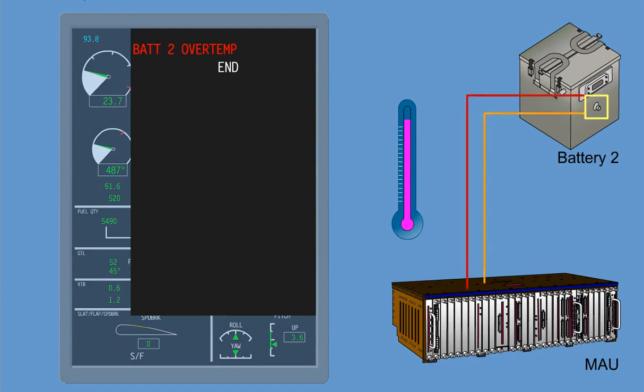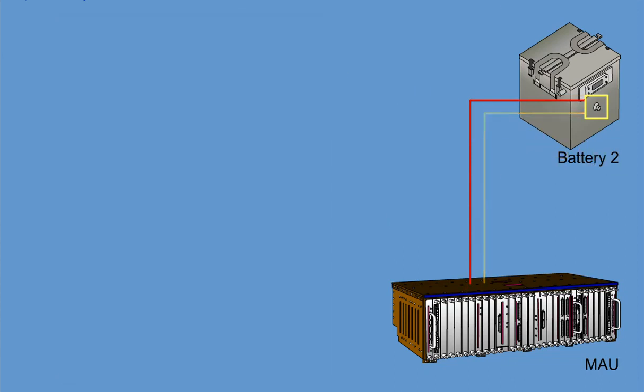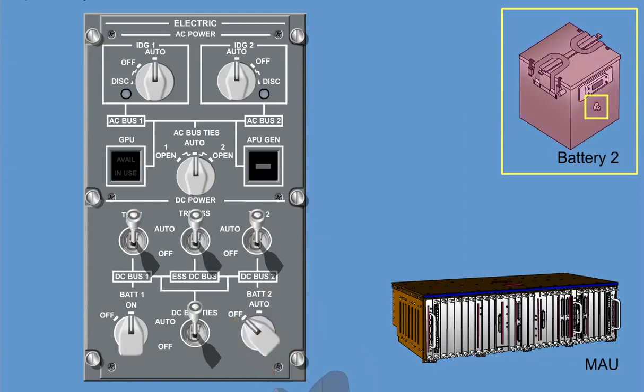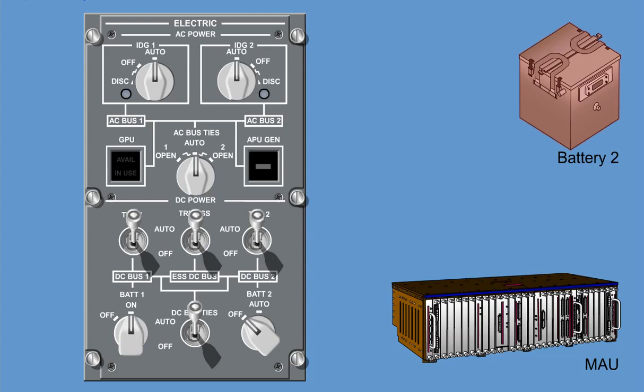The higher of the 2 temperature values sensed is the one utilized for indication and alarm. Whenever a battery over temperature condition is sensed, the pilot should isolate the battery from the charging source. Battery over temperature can generate sufficient heat to damage the battery's surroundings, including those caused by a short circuit at its terminals or to any of its cells. Any mechanical deformation of the battery will be contained within its steel case.